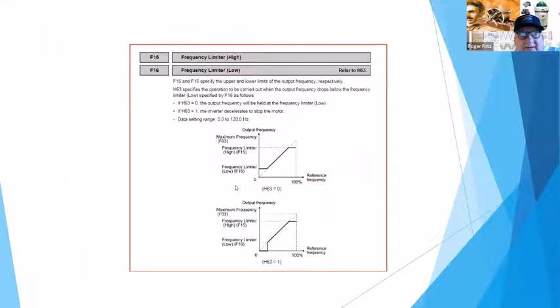But again, my dad always said, use the KISS method. KISS method, keep it simple. Everybody understand what we're doing. It eliminates a lot of problems in the field. We can also control, this is a normal big function that's normally needed, your frequency upper limit and your frequency lower limit. So you can actually set when it turns on, at what level will it immediately go up to a minimum frequency.